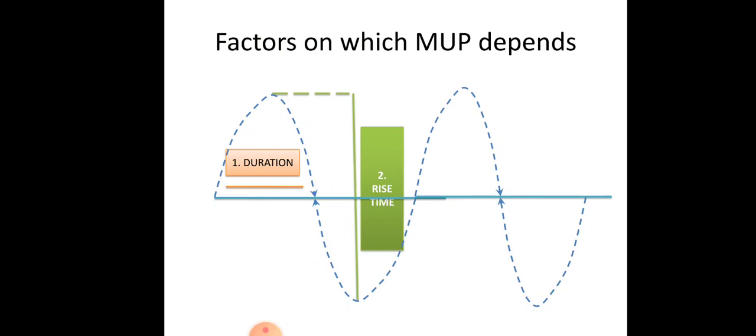How far is your needle located from the muscle fiber? A rise time of less than 500 microseconds is acceptable. A greater rise time denotes the resistance provided by the investing tissue. How much resistance your muscle is providing to the needle is the rise time.